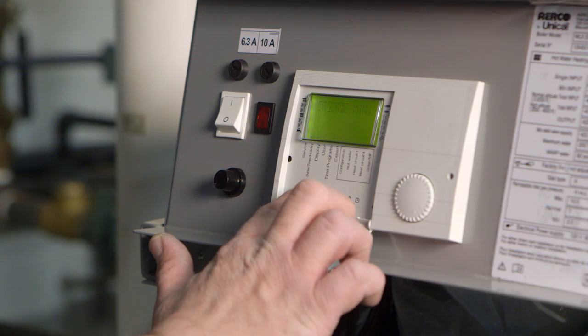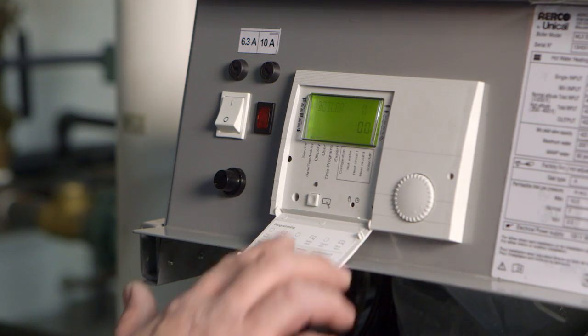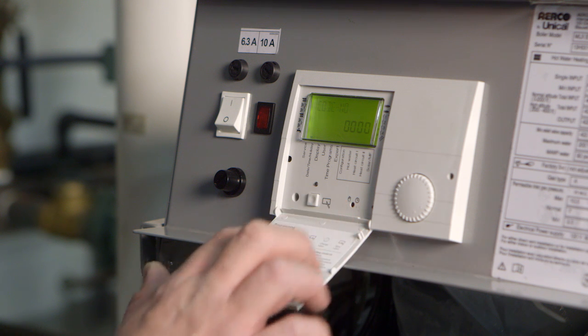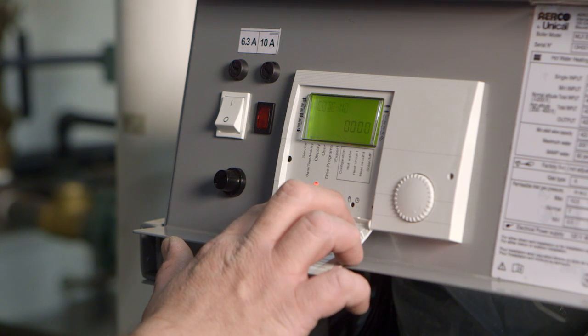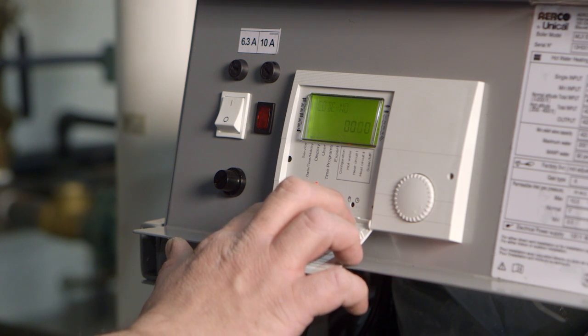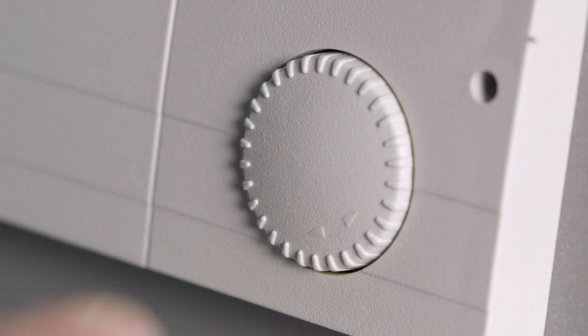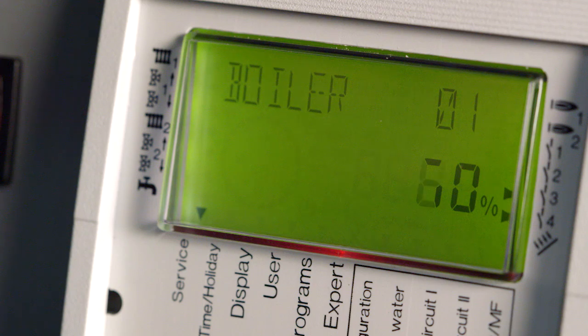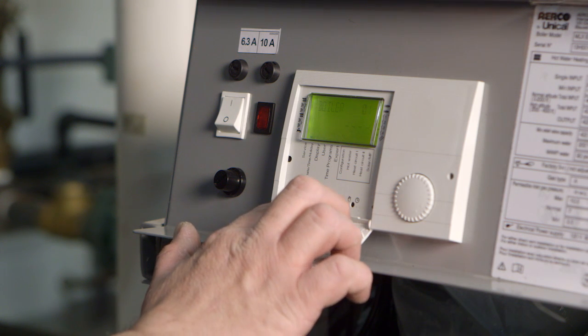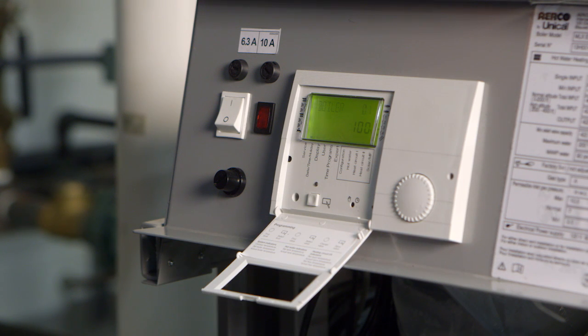On the control panel, access your unit's service mode and use Cascade Manual to turn all burners to 100% fire. Measure the gas pressure with all of the burners in operation. Verify that your unit has the proper gas pressure readings.